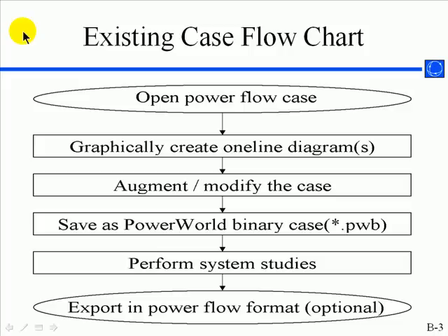Typically the procedure you might go through would be to open a PowerFlow case from a text-based source, create or edit a one-line diagram using the graphic interface discussed in the first training session, then augment the data with supplemental information such as generator cost models or reactive power capability curves. You can save the work in a binary PWB format, then perform advanced studies using tools like contingency analysis, available transfer capability, and optimal power flow. When finished, you might export the data back into a text-based format such as a PTI RAW file or EPC file.